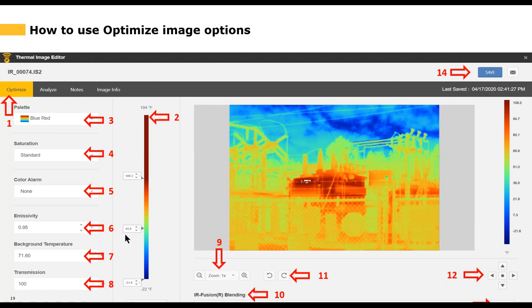In this example, the hot point is 109, the cold point is negative 21.6, and the level (midpoint) is 43.8. Next we have Palette — currently the Blue-Red palette is selected. A palette is simply a color scheme. Infrared cameras and software provide a choice of color palettes that help quickly distinguish thermal variations and patterns in an image. You can select a palette while in the field and then change it back in the office using our software.